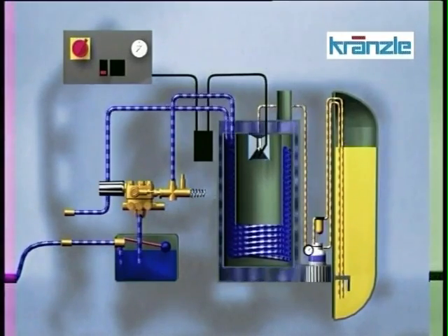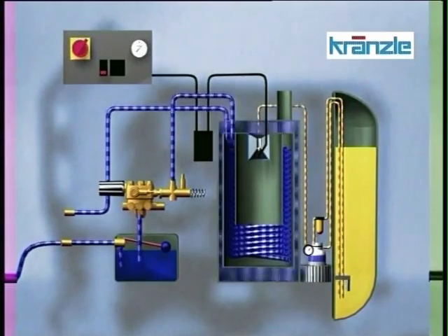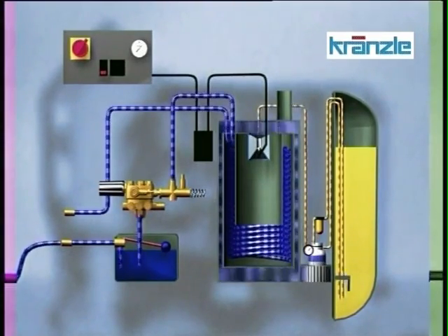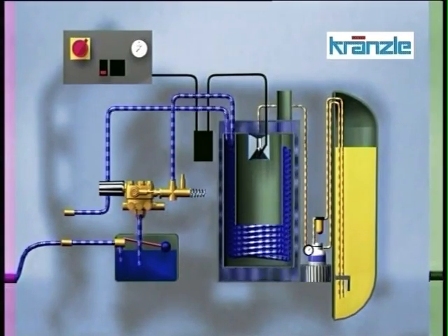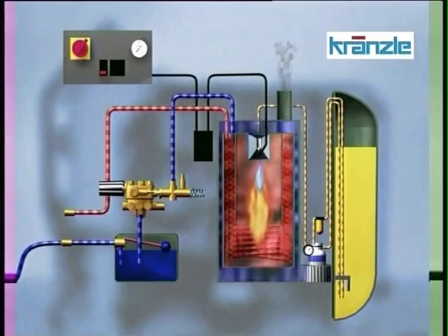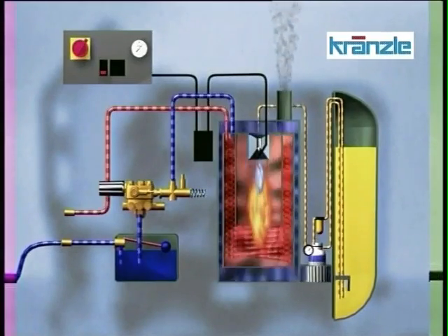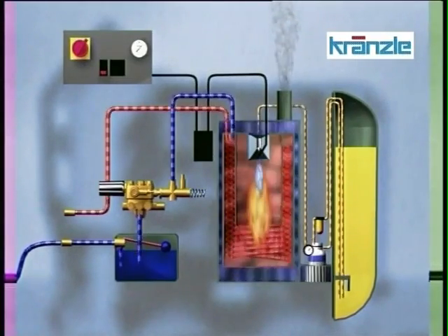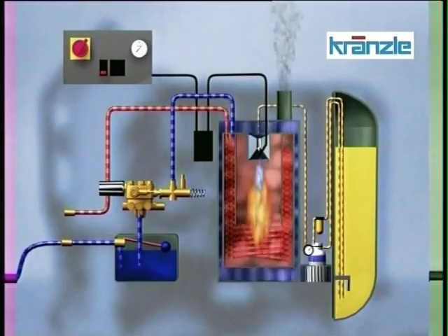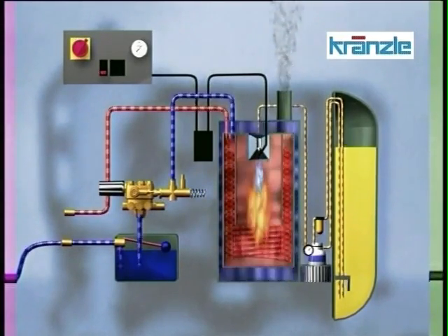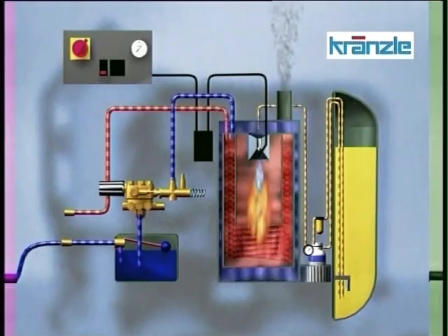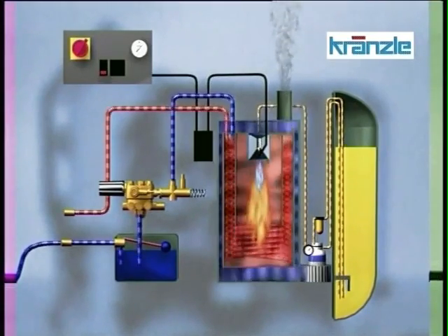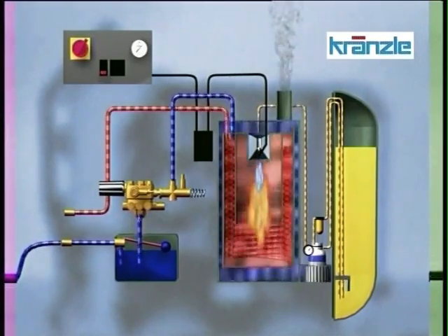At the underside of the pump, fresh air is sucked in, directed into the combustion chamber and preheated. Fuel is injected through a nozzle and mixed with the air. And finally, the electrodes ignite this mixture. The flame burns from the top to the bottom, and the resulting hot gas flows past the heating coil, thus heating the water. The exhaust gases are released through the chimney.